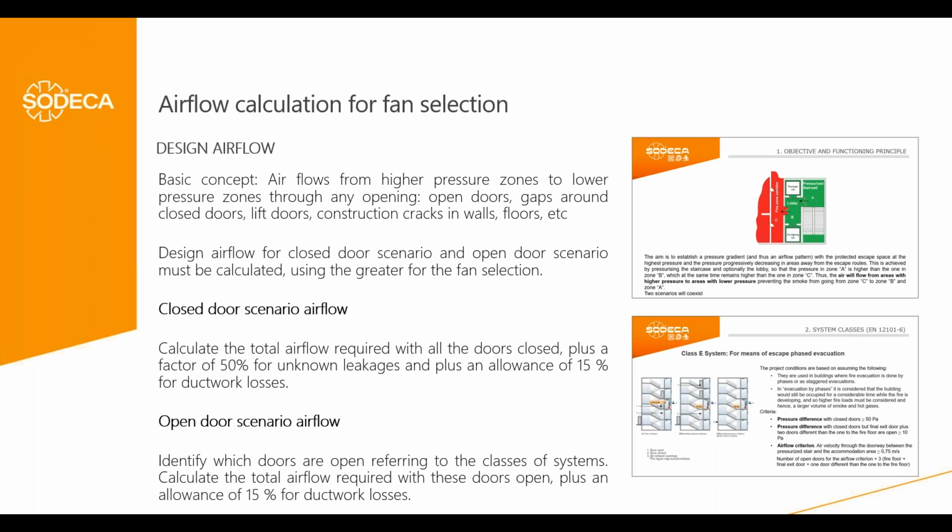Okay, and about the calculation, typically we have the calculation for these two situations: closed door scenario and open door scenario. Part 13 has an annex with examples of calculation. I recommend reading this annex, because it's a good example that, if one follows it, one understands how the calculation is done.